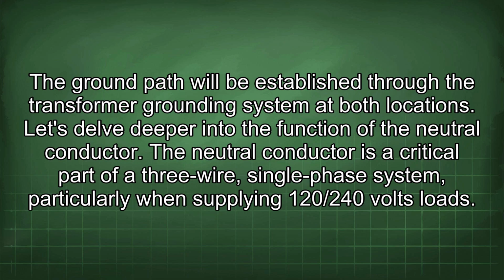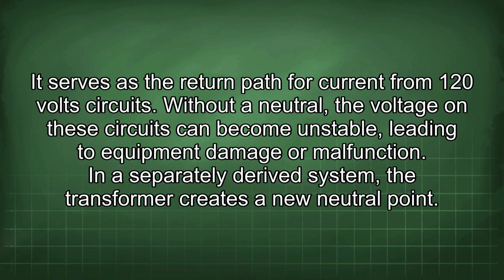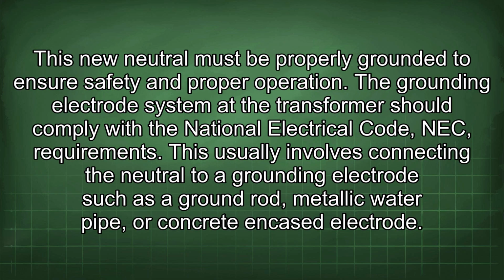Let's delve deeper into the function of the neutral conductor. The neutral conductor is a critical part of a three-wire, single-phase system, particularly when supplying 120/240 volts loads. It serves as the return path for current from 120-volt circuits. Without a neutral, the voltage on these circuits can become unstable, leading to equipment damage or malfunction. In a separately derived system, the transformer creates a new neutral point. This new neutral must be properly grounded to ensure safety and proper operation.